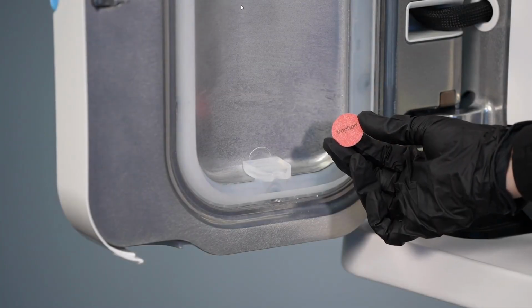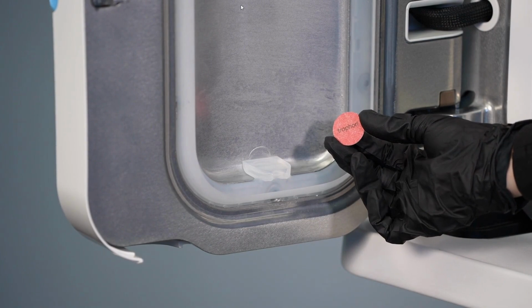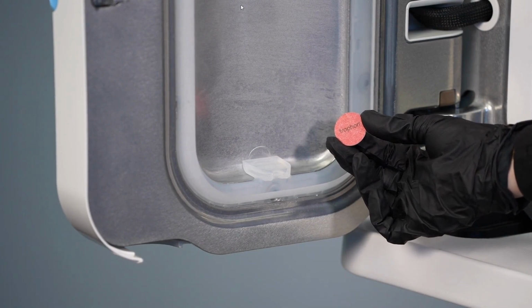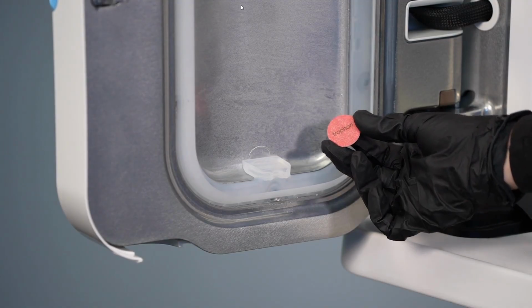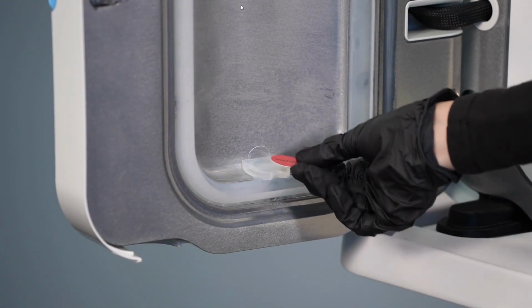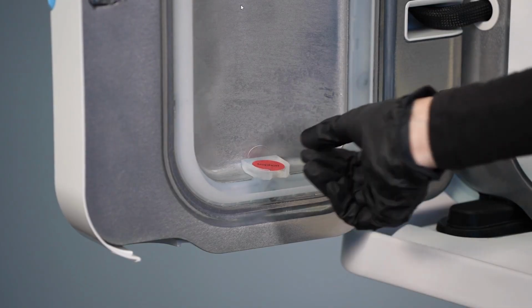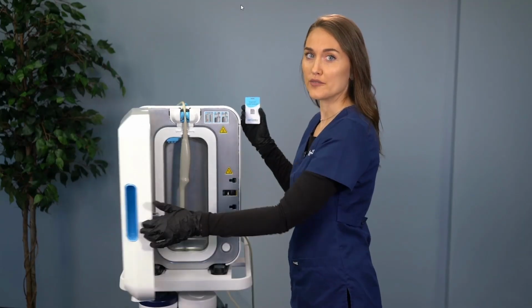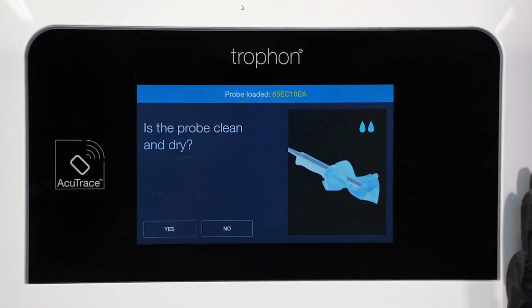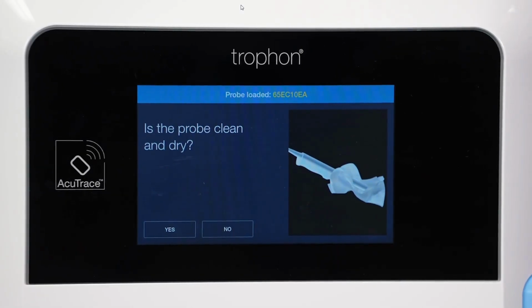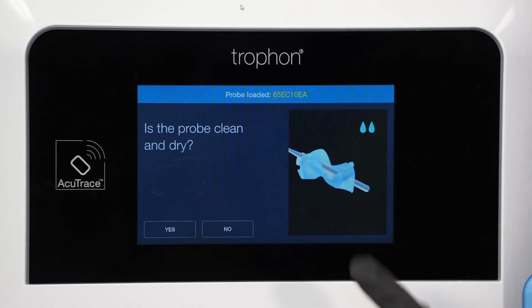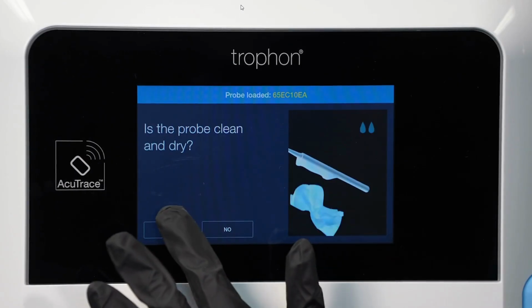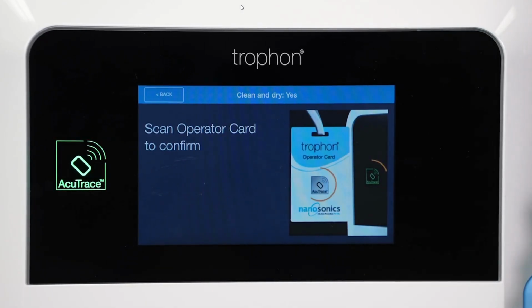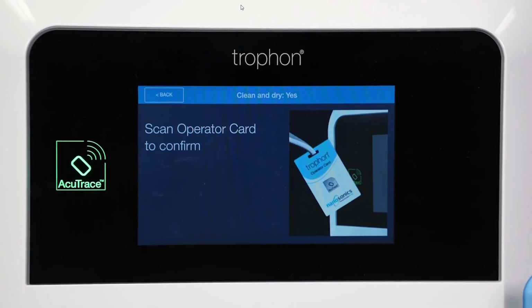Once your probe is appropriately loaded into your chamber, you will take a new chemical indicator from its box. Place chemical indicator red side up in the slot in your door. You can then go ahead and gently close your door. And then we can follow our on-screen prompts. So our screen is asking, is the probe clean and dry? We can go ahead and pick yes. And then it's asking us to scan our operator card to confirm.